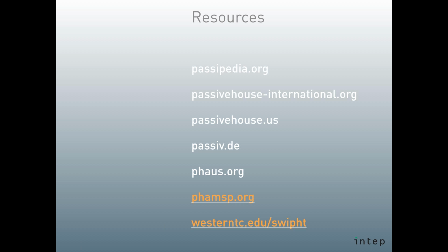And that's an interesting one too. We did talk quite a bit with Fujitsu about that, because they can do that. It's possible to connect the heating, cooling, ventilation system together. The problem that you run into is that they have completely different CFM requirements. So while the ventilation system may be at 80 or 100 CFM, the heating cooling system, when it's running at full steam, may provide 400, 800 CFM of throughput. So they're not compatible. And that's where the story stops for me, because at that point you need to put in smart dampers and stuff like that, because otherwise you're going to start sucking on your ventilation setup, which could wreak havoc with the internals of that machine. And we decided to keep those two separate.